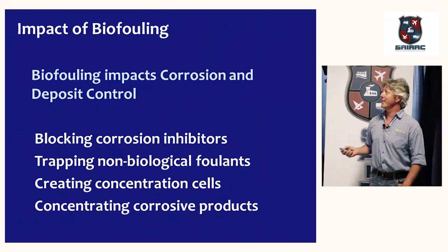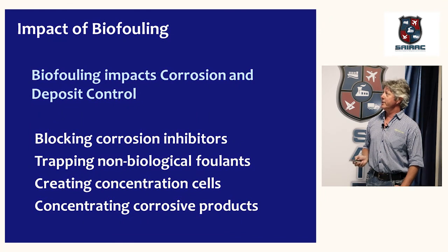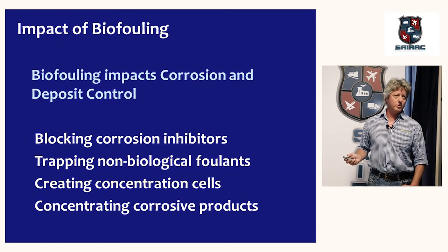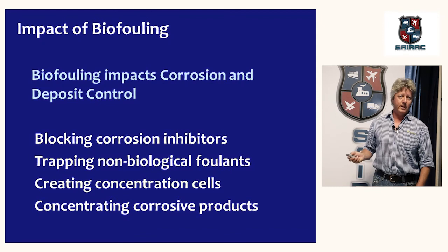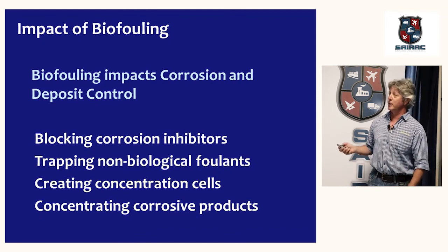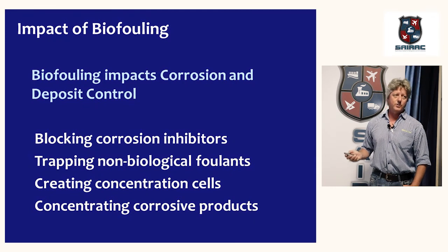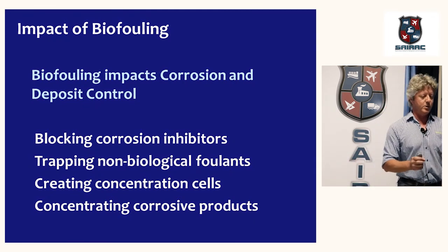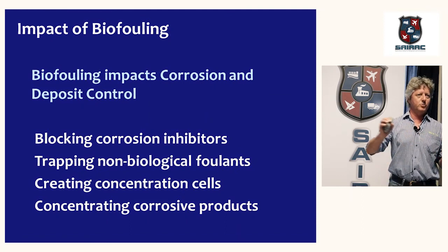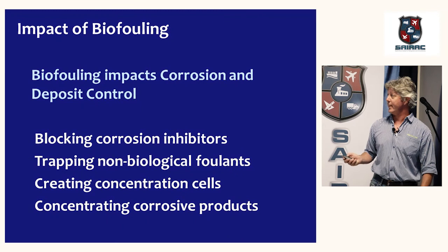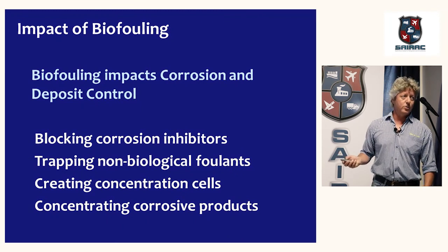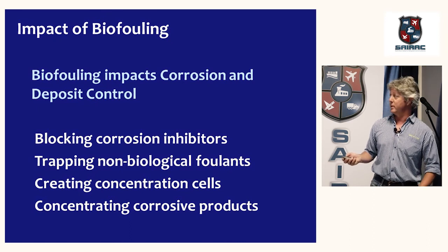The impact of biofouling. Biofouling impacts corrosion and deposit control. It blocks corrosion inhibitors, which we add to the water in order to prevent corrosion. It traps non-biological foulants, in other words, any dust that gets sucked into the cooling system gets trapped in this biofouled mess around your system. It creates concentration cells. Now, a concentration cell is where you get a concentration difference between different kinds of salts in your system, and that will lead to corrosion taking place. So it also does concentrate your corrosive products, which is the metabolites of the bacteria.